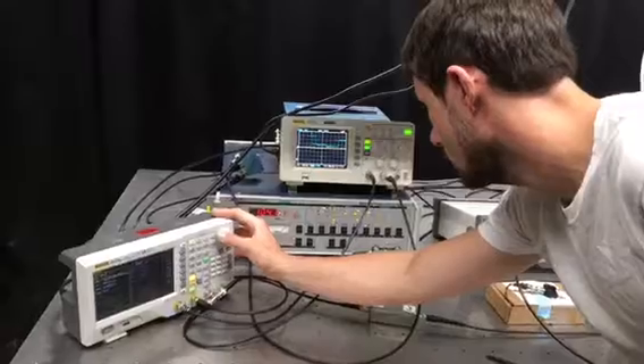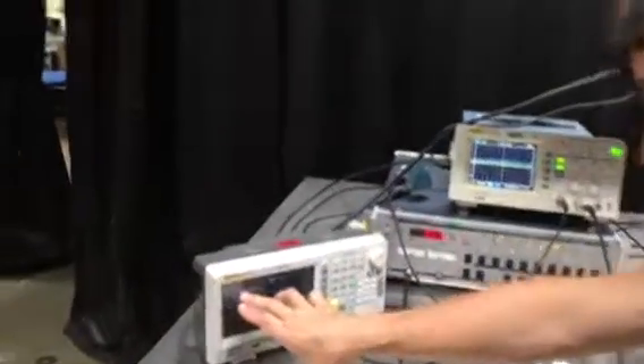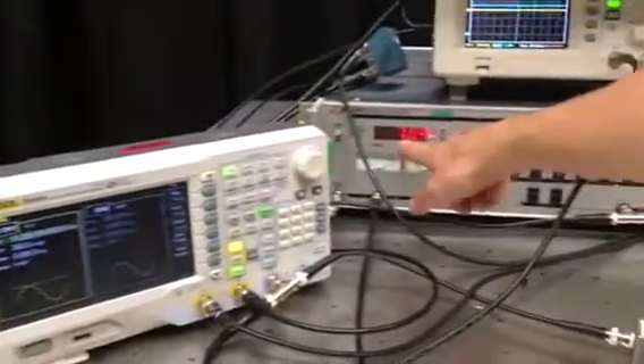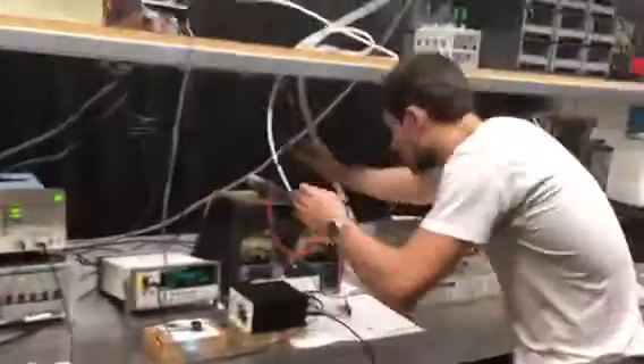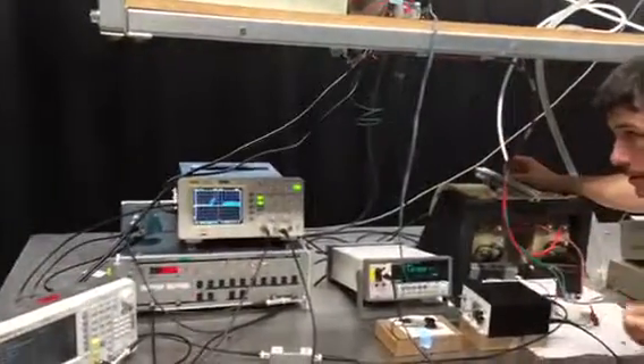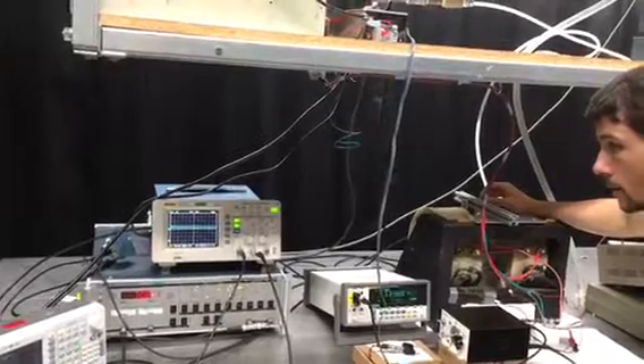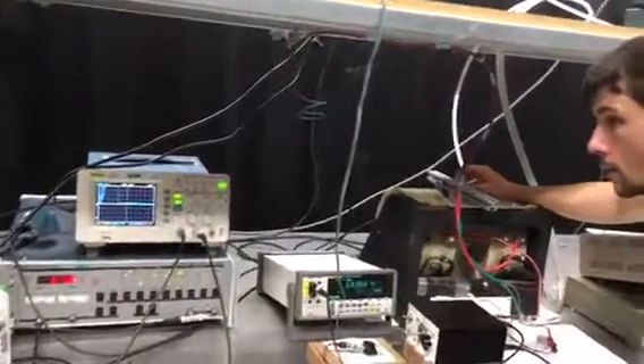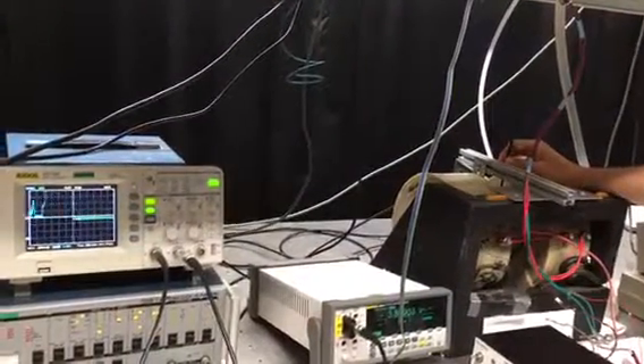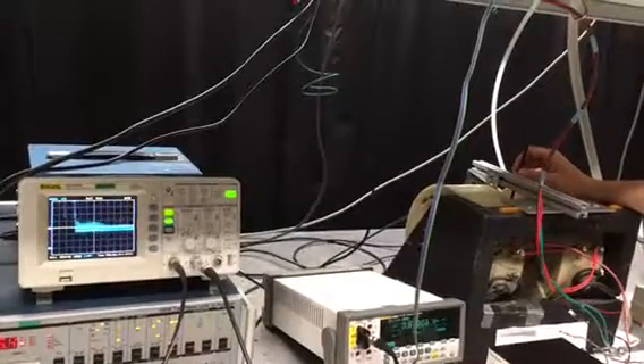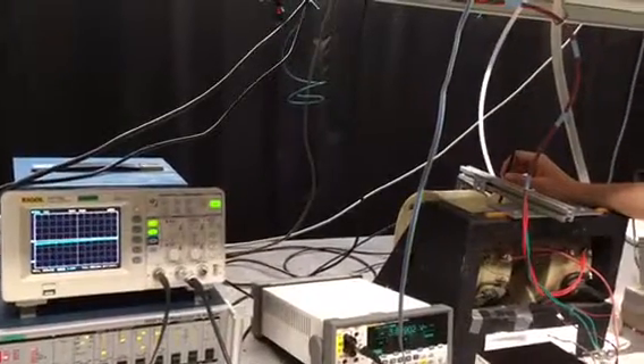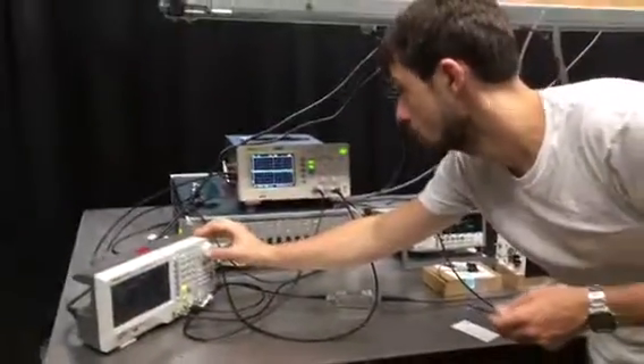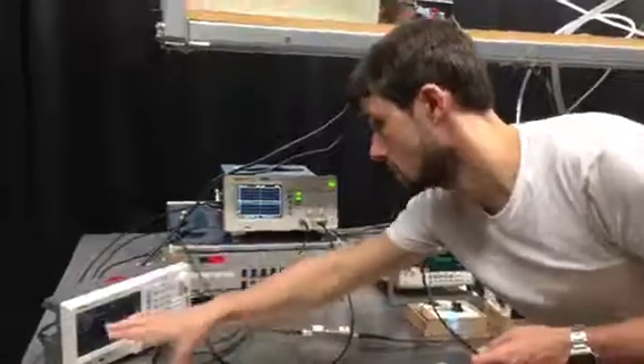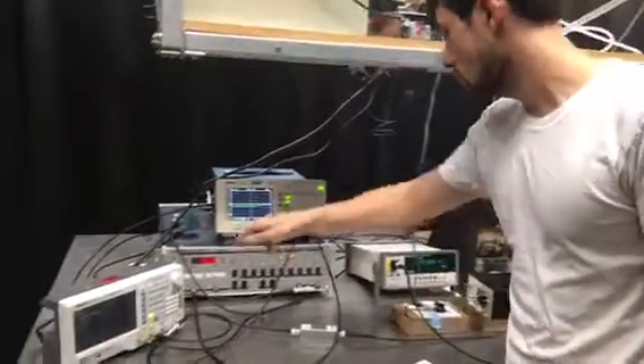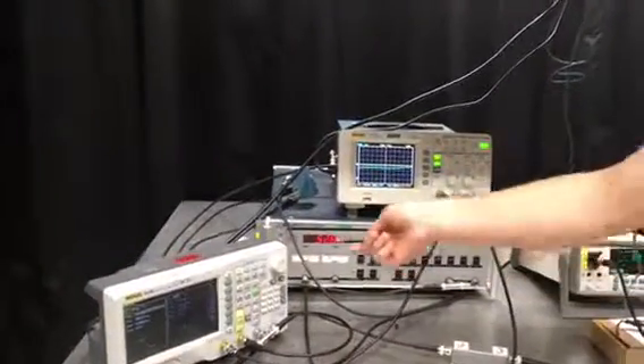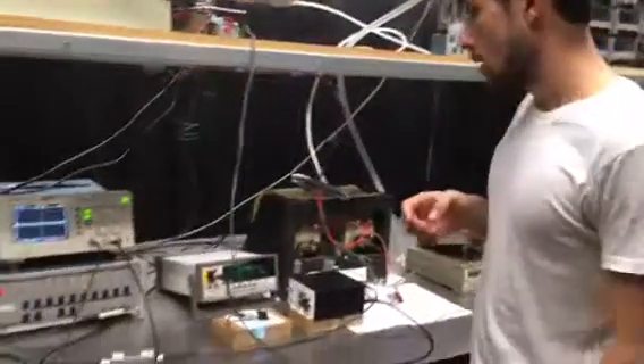So by retuning the frequency ever so slightly upwards, we've brought the feed through back down to a reasonable value. We can also try adjusting the resistance a little bit. Getting better. Getting better. Okay, so relatively little bit of recalibration and we're back into normal range. Since we're at the 100 microvolt scale, it's no longer in overload. So now we can begin a search.